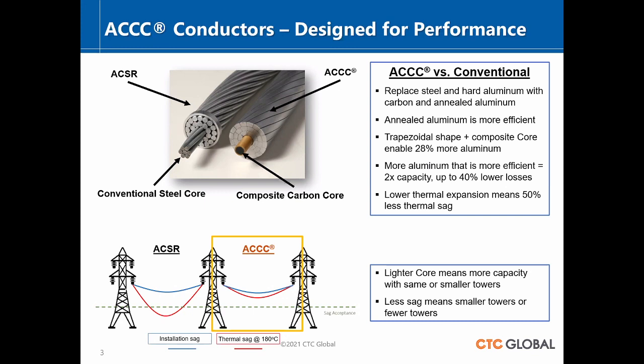Here, this will heat up. It will sag, but tremendously less. In fact, it's called a low sag conductor. Because it is lighter in the center, and we're able to use the trapezoid wire, we get more aluminum in the same diameter. So for the same diameter, it turned out to be the same weight. That gave us some very unique opportunities as well. We'll talk about reconductoring by literally just changing the wire that's up there with an advanced conductor, ACCC, that gives you more capacity, immediately better loss reductions, more efficiency, and 2 times the capacity.